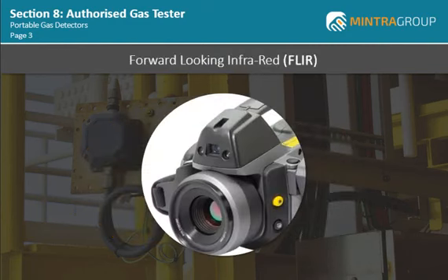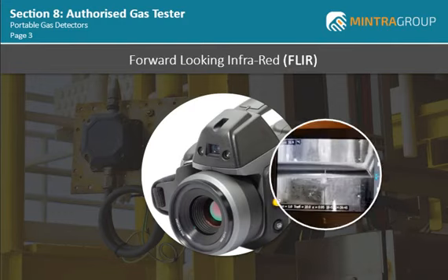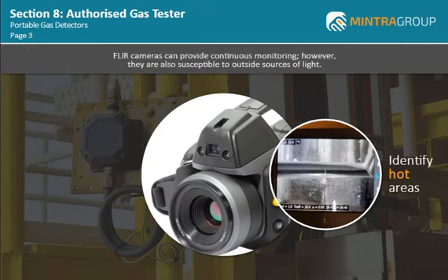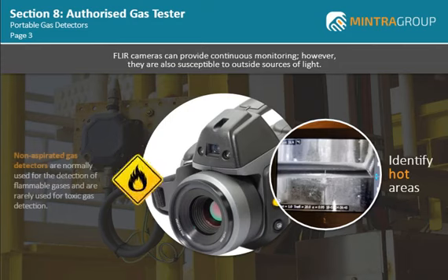Forward-looking infrared uses the natural reflection of surrounding objects to analyze the absorption of the gas. FLIR cameras can also be used to identify hot areas where a fire may have been initiated, sounding an alarm in the control room for investigation. FLIR cameras can provide continuous monitoring, however they are also susceptible to outside sources of light, such as flash photography, which may cause spurious alarms.